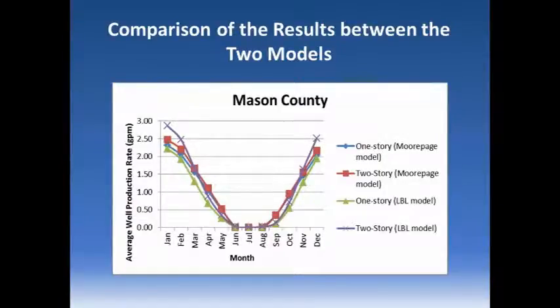You have two cases, right? In one scenario, you figure you've got to pump the water anyway, so you're basically saying you have this thermal energy loop you're pumping regardless, and now you extract heat out of it—the coefficient of performance is pretty favorable because of the starting temperature. In other cases, where you might not have pumped the water in the first place, you're now adding that pumping as extra energy input.